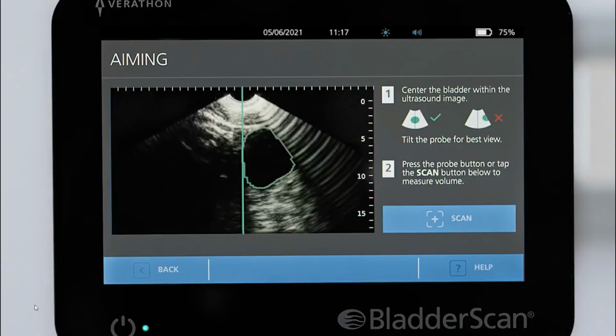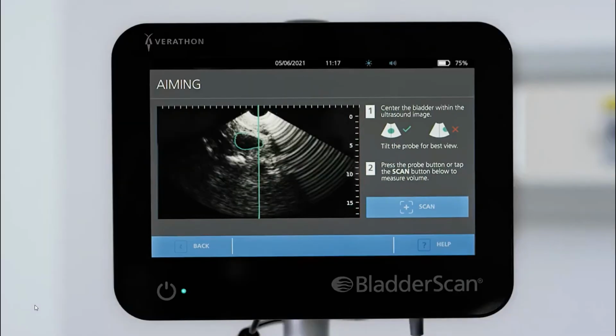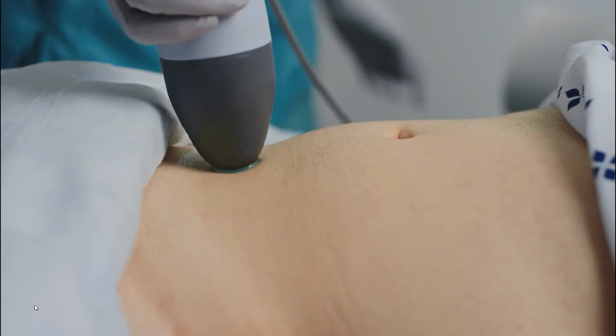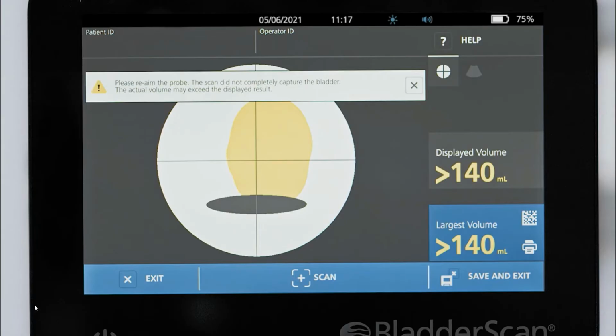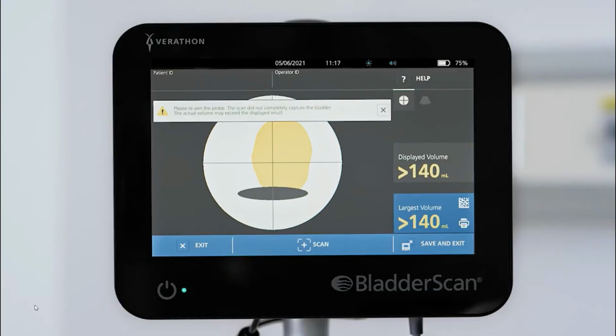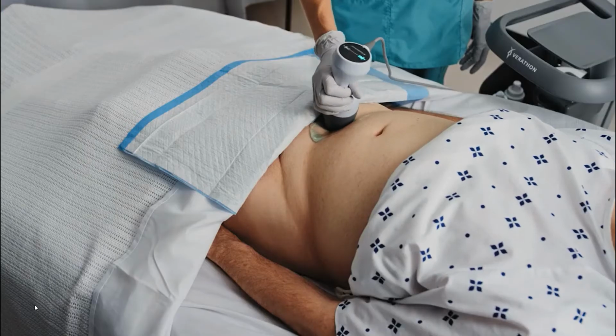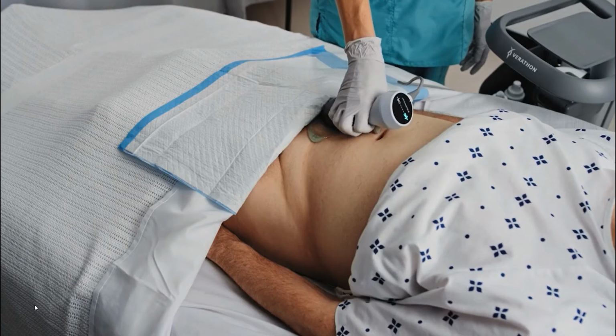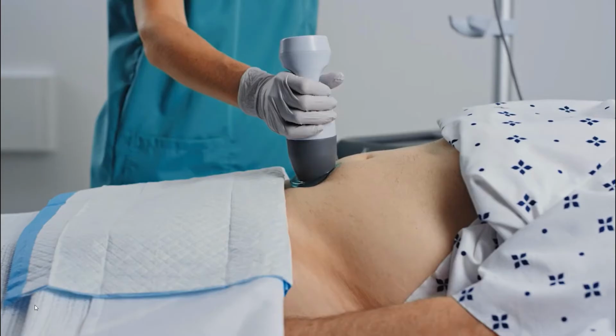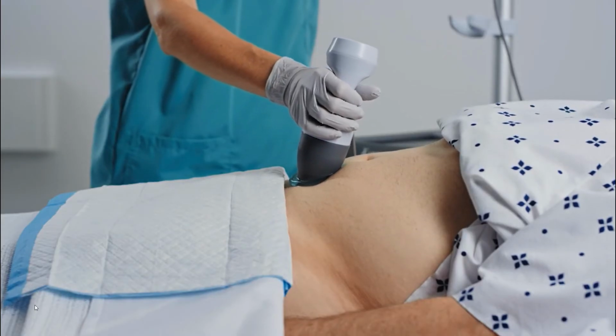The probe was lifted during the scan, or there were excessive air gaps because there wasn't enough gel at the probe tip. If a gray area appears with the yellow bladder image, this indicates that the pubic bone is inside the field of view. Although the bladder may be centered, there is a possibility the pubic bone is obscuring part of the bladder. This can occur if the probe was tilted too far towards the feet, if the patient has a small pelvis, or if the bladder is small or located deeper.